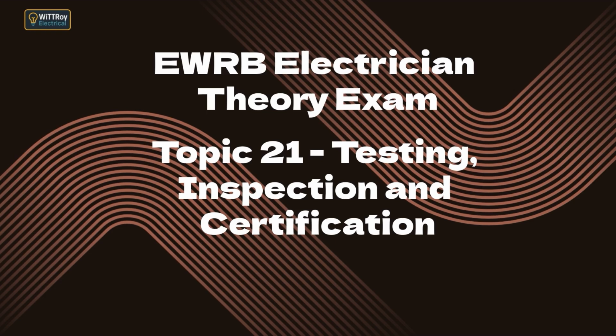Examples include mains switchboard upgrades, mains work involving earthing or bonding, works that affect safety of main systems, installations in hazardous areas, medical cardiac locations, any work requiring certification that the main system is correct. The electrician does the work and does the tests, but the inspector must independently check and sign off the job before it can be connected.